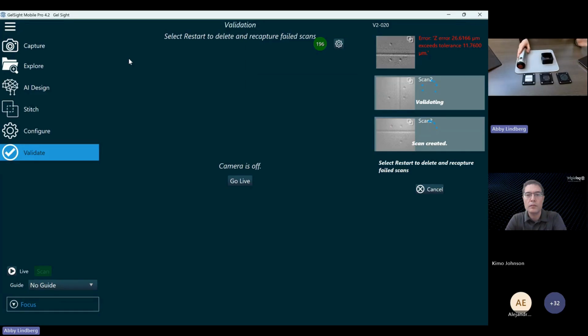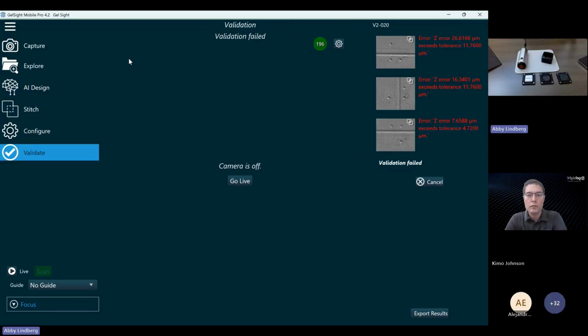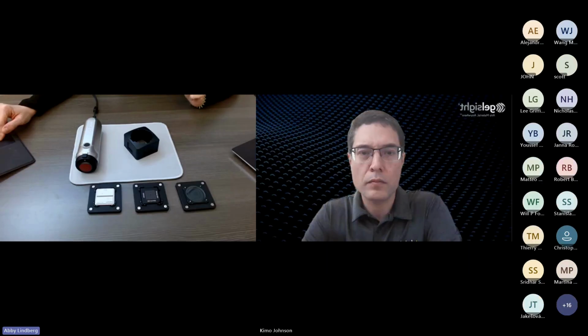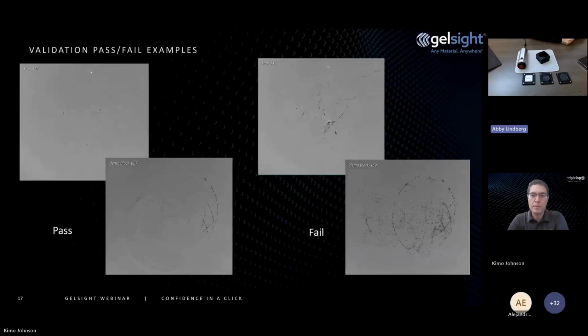So we can see we've already failed the first scan. So we failed validation at this point. It's going to still run through the process of measuring the other features for all of the scans. But the process for validation failure is to try recalibrating and then validating again. And if you fail one more time, then you would want to replace the gel. So this is what's giving you that quantified reason to replace your gel. And I think we've got a couple images of that really highlight when to replace a gel, and maybe when you pass and when you fail validation, that we'll pull up here.